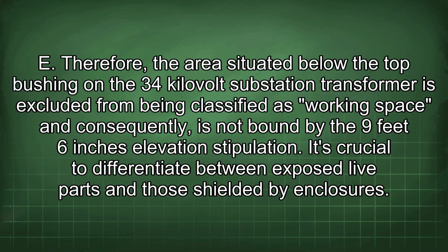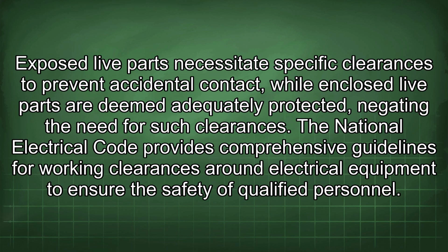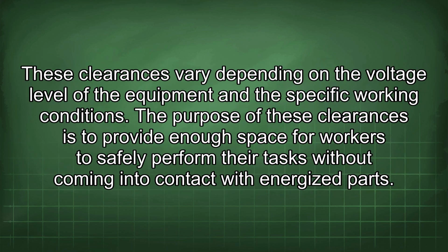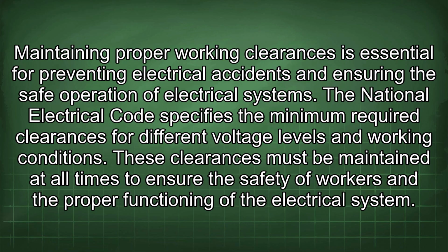It's crucial to differentiate between exposed live parts and those shielded by enclosures. Exposed live parts necessitate specific clearances to prevent accidental contact, while enclosed live parts are deemed adequately protected, negating the need for such clearances. The National Electrical Code provides comprehensive guidelines for working clearances around electrical equipment to ensure the safety of qualified personnel. These clearances vary depending on the voltage level of the equipment and the specific working conditions. The purpose of these clearances is to provide enough space for workers to safely perform their tasks without coming into contact with energized parts. Maintaining proper working clearances is essential for preventing electrical accidents and ensuring the safe operation of electrical systems.